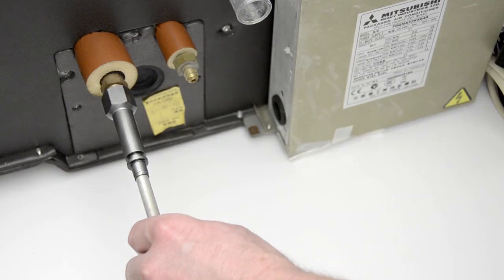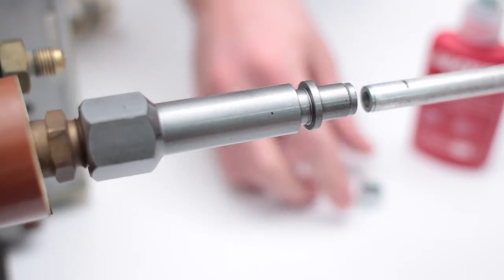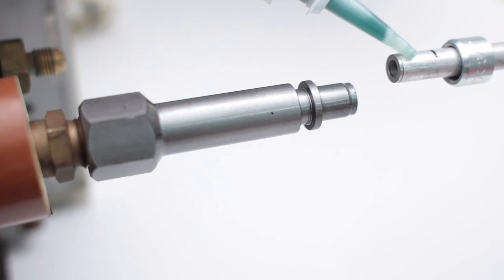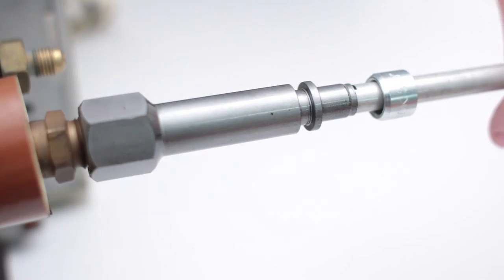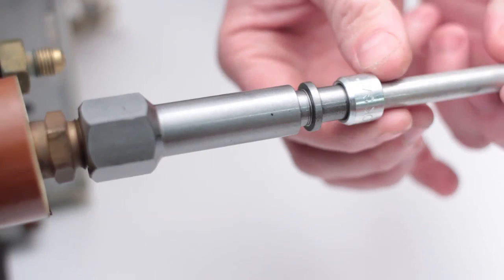Insert the end of the pipe into the reflock joint body and then mark the pipe. Slide the nut onto the pipe with the beveled edge facing the body of the connector. Apply lock preparation fluid to the pipe, then fit the pipe into the body of the connector, twisting it to ensure an even spread of the lock preparation fluid.